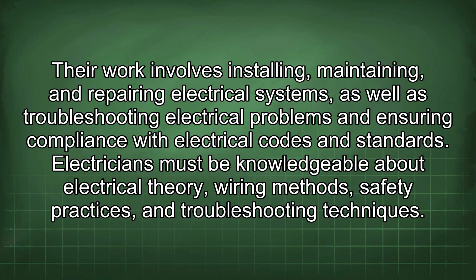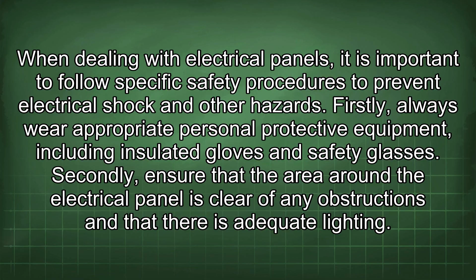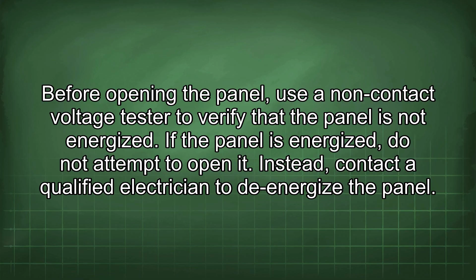When dealing with electrical panels, it is important to follow specific safety procedures to prevent electrical shock and other hazards. Firstly, always wear appropriate personal protective equipment, including insulated gloves and safety glasses. Secondly, ensure that the area around the electrical panel is clear of any obstructions and that there is adequate lighting. Before opening the panel, use a non-contact voltage tester to verify that the panel is not energized. If the panel is energized, do not attempt to open it. Instead, contact a qualified electrician to de-energize the panel.